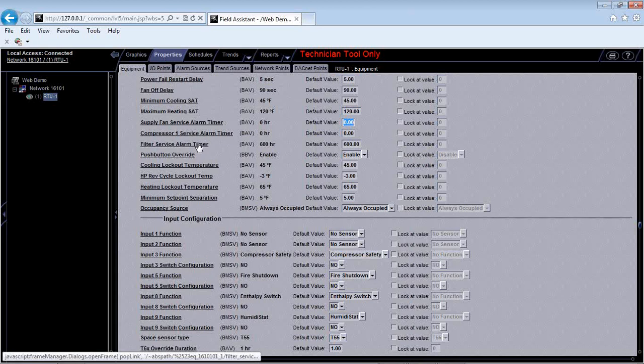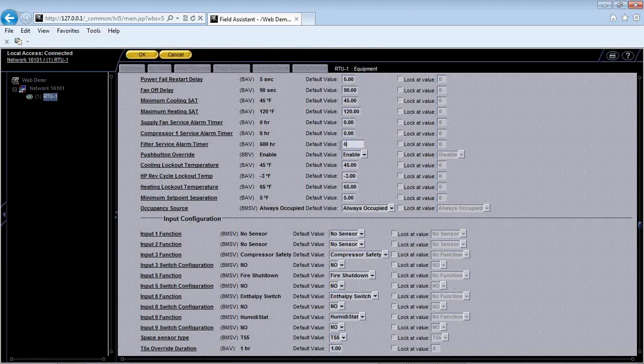So one thing to note is if you're commissioning one of these controllers and you're doing it into a third-party system, you want to take these values and you want to send them to 0, okay? Because you don't want your controllers and your alarms and timer alarms interfering with the third-party building automation system, okay? Because you don't want them to see this BACnet point of, I have a filter alarm, but there's really nothing actually confirming that your filter is an alarm. It's just a timer that went off.